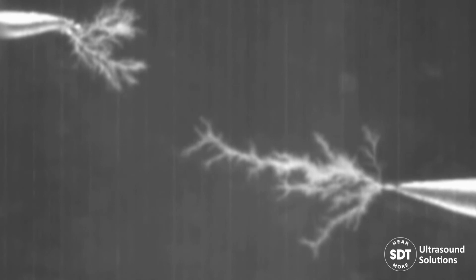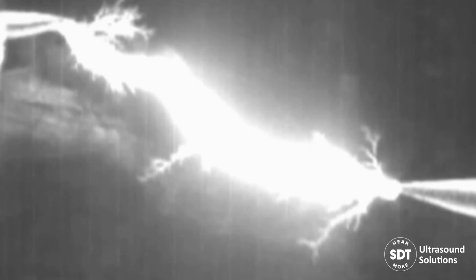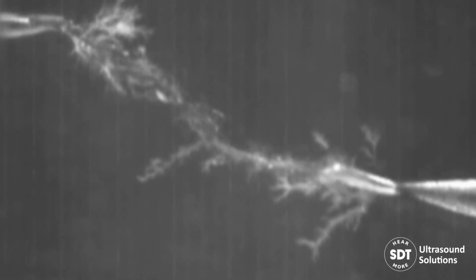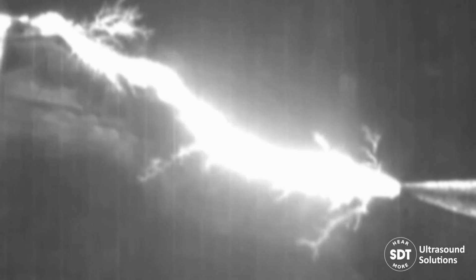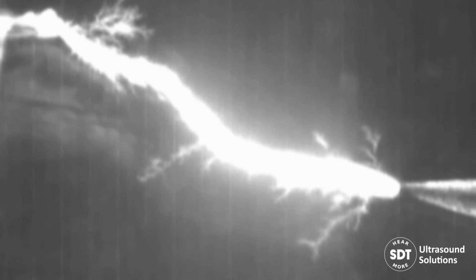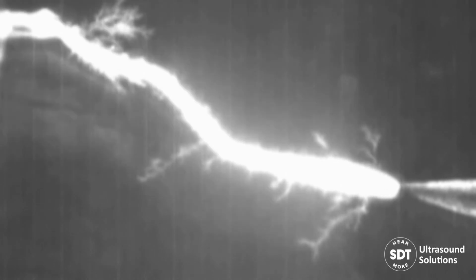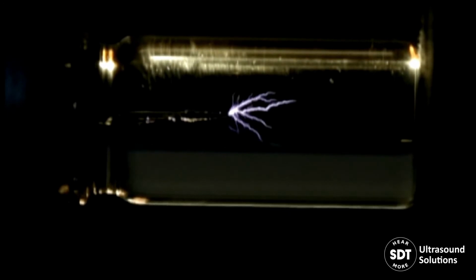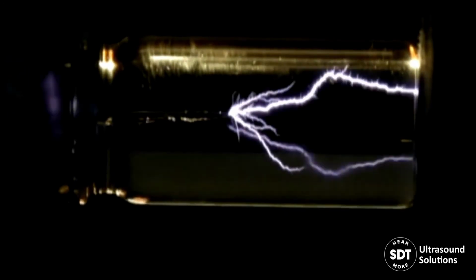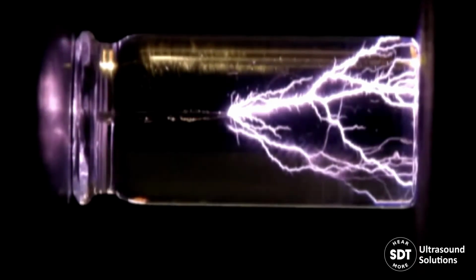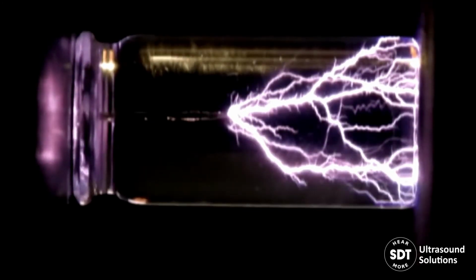Now, if you've ever walked into a substation and noticed the smell of ozone, then you've witnessed the presence of partial discharge firsthand. Partial discharge has many causes, including voids in solid insulation, often caused during manufacturing, mechanical breakdown or damage to insulation, sometimes caused during installation, or what we call poor workmanship, design defects, such as poor stress control or irregularities, or a combination of factors that are characteristic of assets getting older and ultimately breaking down.